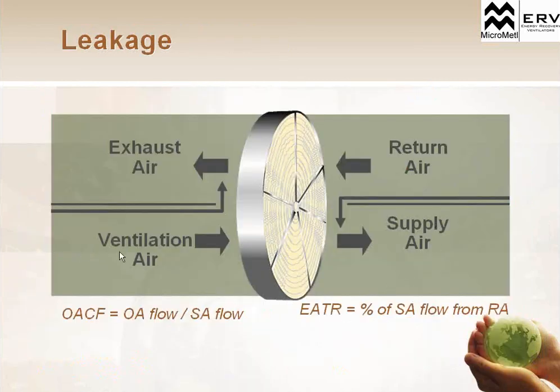If we look real quick at this leakage slide, leakage basically means when I'm sending exhaust air from the building out of the wheel across outside of the building, some of the air obviously wants to follow the path of least resistance. So instead of going through that wheel, it creeps around and sneaks around before it goes through the wheel and gets back into the supply airstream. That's bad because we're not getting as much ventilation air as we need to, right? We're just returning air back into the system.